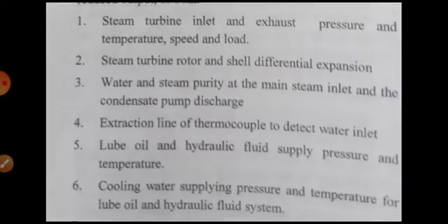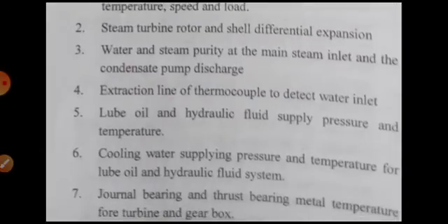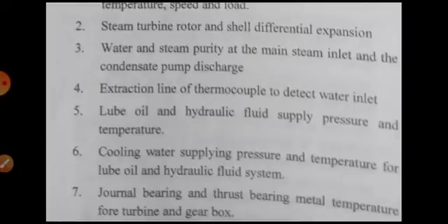Steam turbine inlet and exhaust pressure and temperature, speed and load, steam turbine rotor and shell differential expansion, water and steam purity at the main steam inlet and the condensate pump discharge, extraction line and thermocouple to detect water inlet, lube oil and hydraulic fluid supply pressure and temperature, cooling water supply pressure and temperature for the lube oil and hydraulic fluid system, journal bearing and thrust bearing metal temperature for turbine and gearbox.